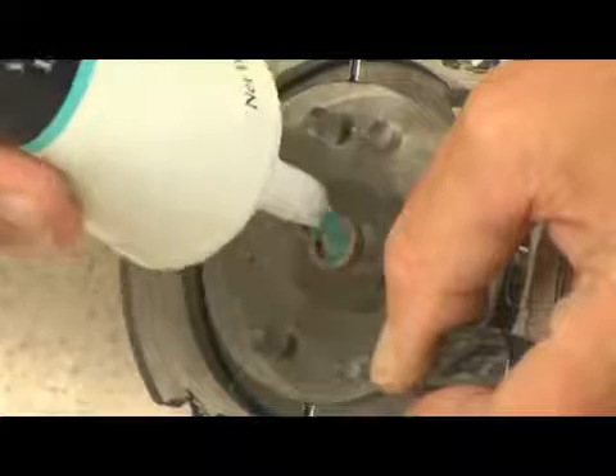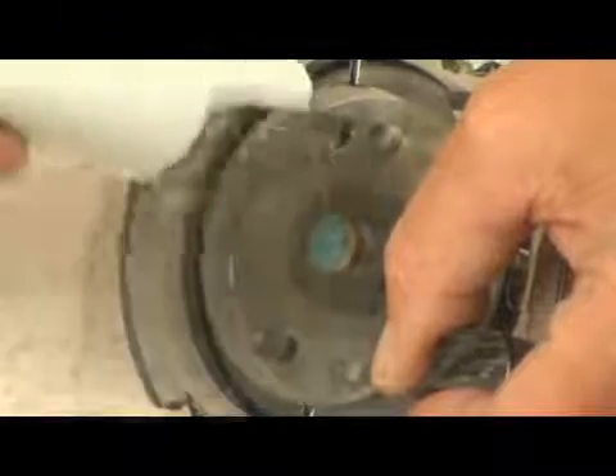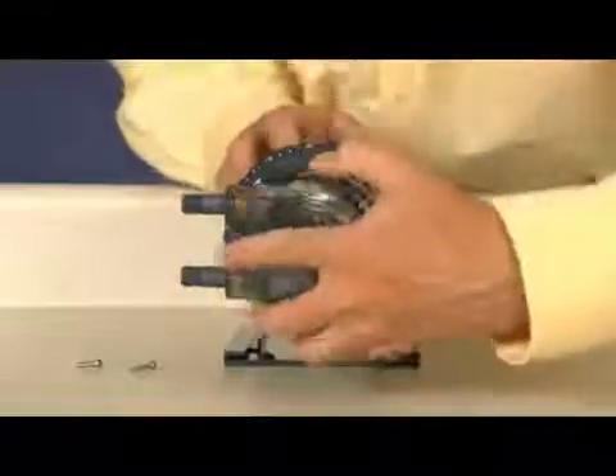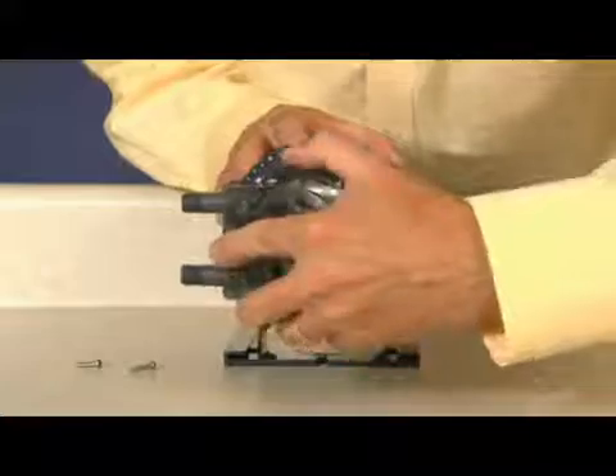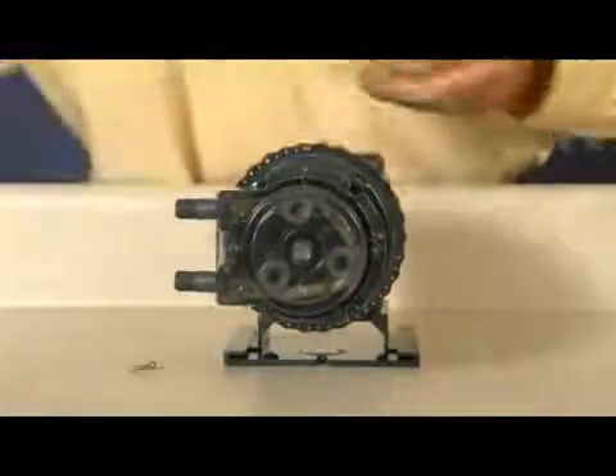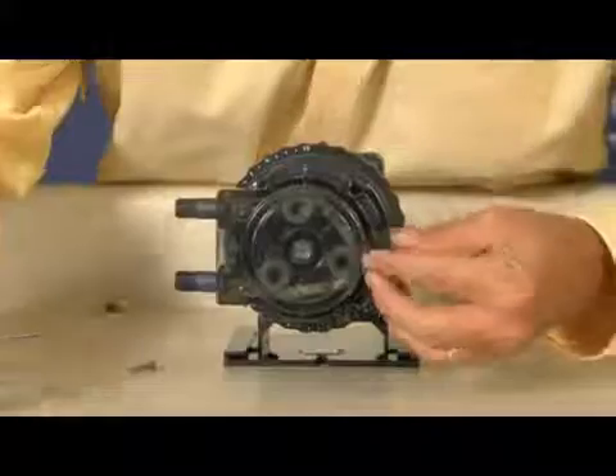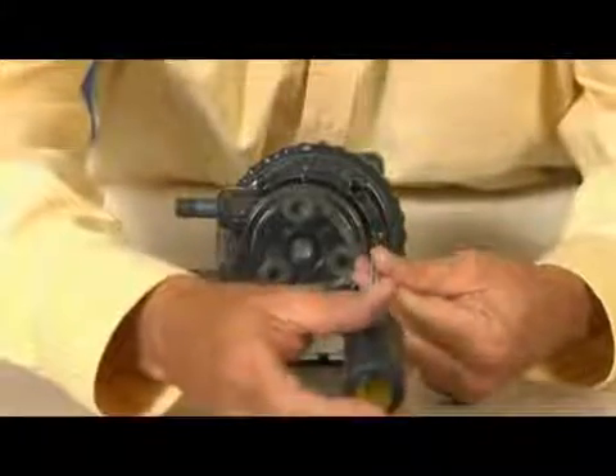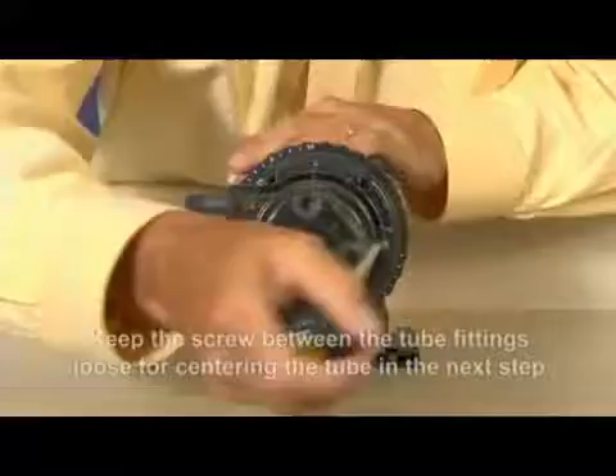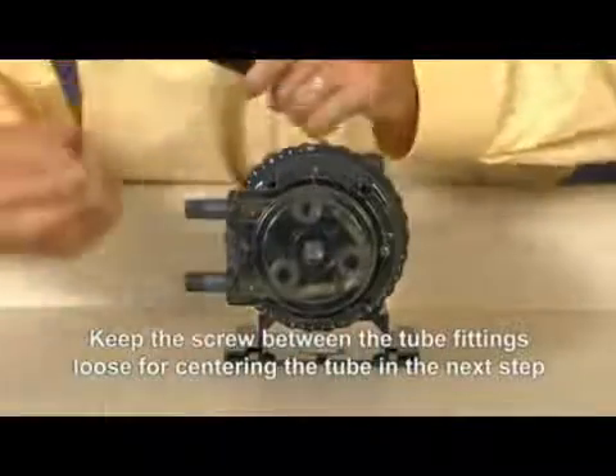Apply a small amount of AquaShield to the cover bushing only, and replace the cover in 2 screws, leaving the front screw between the fittings loose. The cover screws are self-tapping and must be backed in to locate original threads before securing. If a screw boss is stripped, use alternate bosses that are positioned opposite from each other. Never secure the cover plate with more than 2 screws. The tube housing needs room to flex when the rollers turn so the pump head doesn't crack.